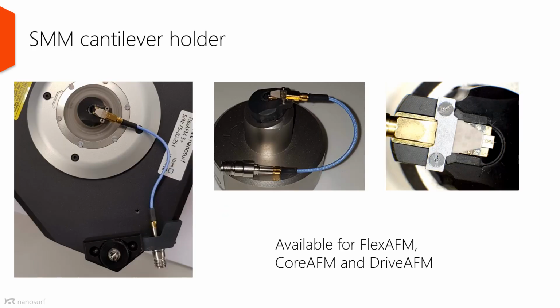Let's say a few words about the hardware. As we already know, the microwaves are best transmitted through the coaxial cables. Once the coaxial structure is broken, the wave goes everywhere in the free space, and it's losing its power. So it's very important to bring the coaxial line as close as possible to the cantilever, and therefore you need a special cantilever holder, which we have built for this purpose. Here's how it looks on our FlexAFM. Here you can see the microwave connectors integrated in the cantilever holder, and here's the PCB, which is a coplanar waveguide to bring the 50 ohm as close as possible to the cantilever. The cable is a low-loss coaxial cable, and it interfaces the cantilever holder with the RF electronics. The connection to the electronics is done via the 3.5 mm SMA connector.